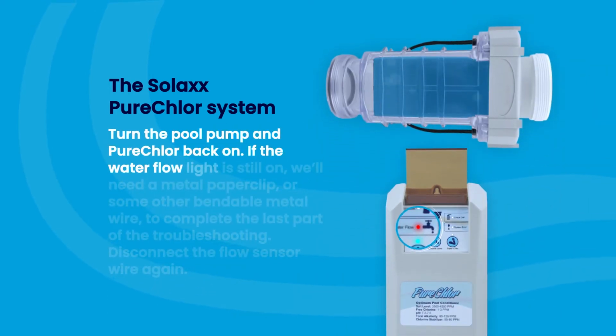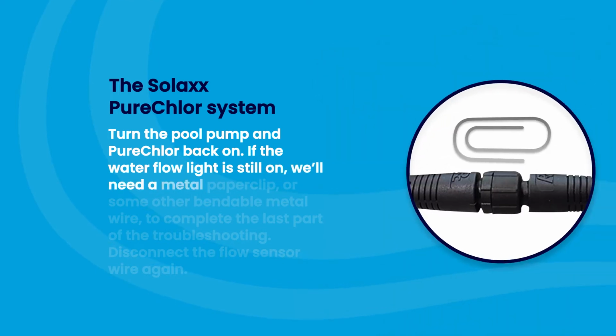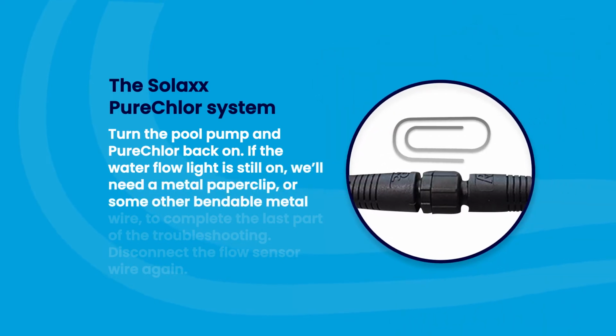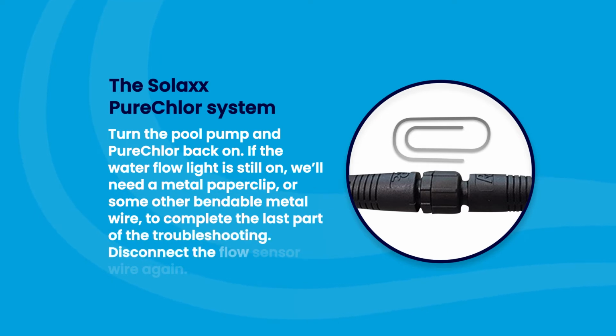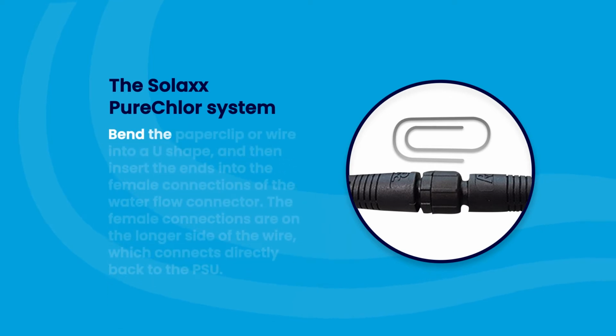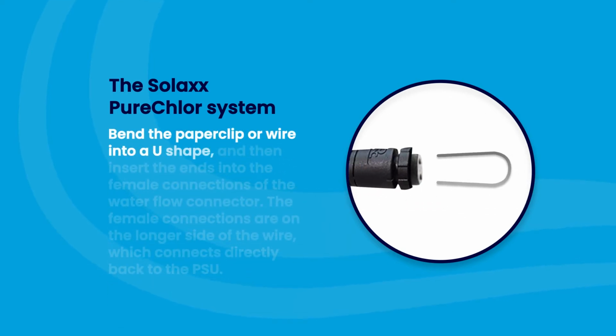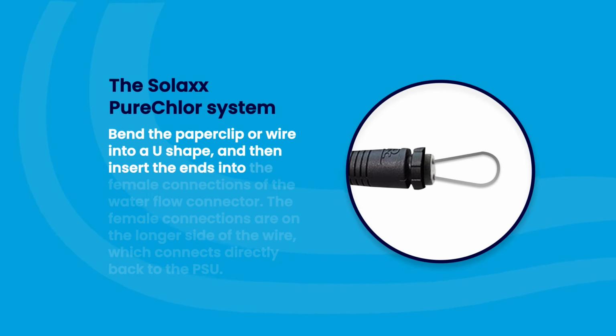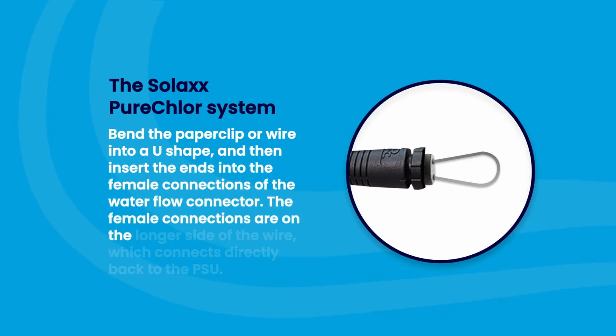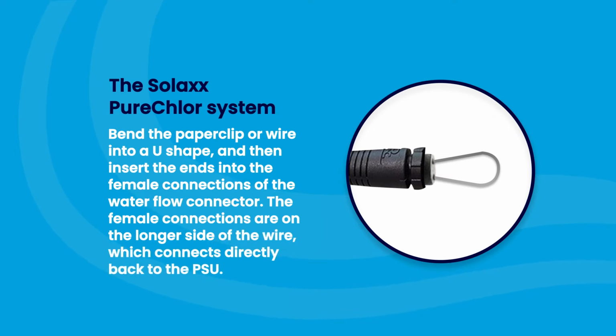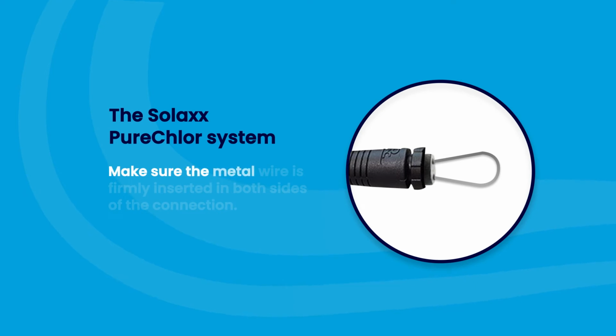If the water flow light is still on, we'll need a metal paper clip or some other bendable metal wire to complete the last part of the troubleshooting. Disconnect the flow sensor wire again. Bend the paper clip or wire into a U-shape, and then insert the ends into the female connections of the water flow connector. The female connections are on the longer side of the wire, which connects directly back to the PSU. Make sure the metal wire is firmly inserted in both sides of the connection.